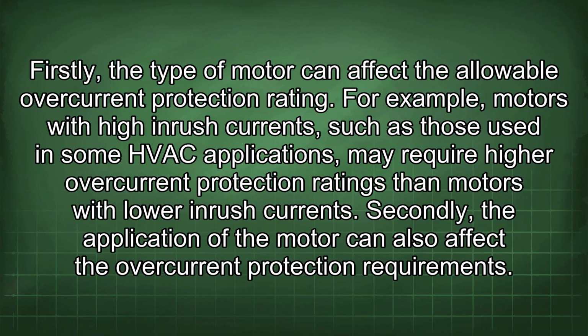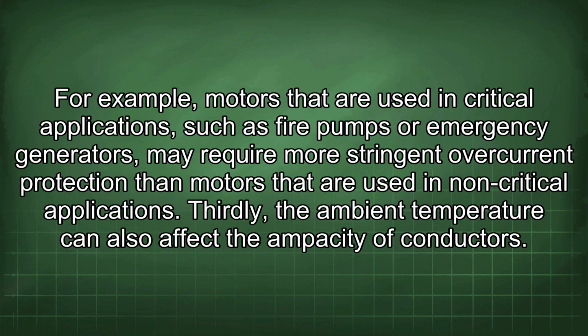Firstly, the type of motor can affect the allowable overcurrent protection rating. For example, motors with high inrush currents, such as those used in some HVAC applications, may require higher overcurrent protection ratings than motors with lower inrush currents. Secondly, the application of the motor can also affect the overcurrent protection requirements. For example, motors that are used in critical applications, such as fire pumps or emergency generators, may require more stringent overcurrent protection than motors that are used in non-critical applications.